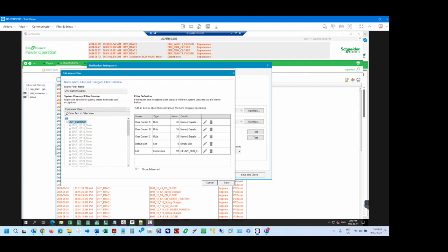Okay, so that's a demand response load shed type scheme. I'm presuming that is somehow built into this; they just need to know how to get to that. Yeah, that's another good example of how best to use a function of the system. I'll look at ways that we can do that, and there again might be multiple, but which is the best and easiest way to go about it? I'm a simple guy. Give me the easiest way. Something we can quickly document and say, here's how you do it, or here's the function block that does it, and if you want to change that set point, 55 megawatts, just change this parameter. That type of thing. Because if we had a hard set, I would want that setting to be able to be changed if you wanted to.